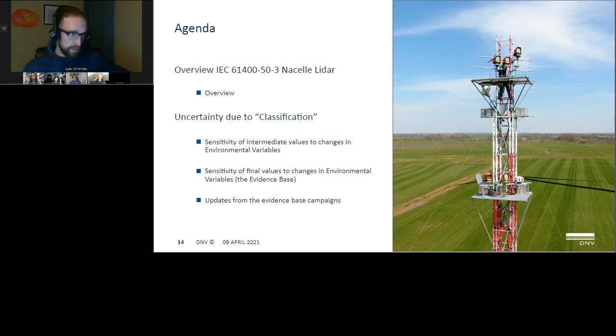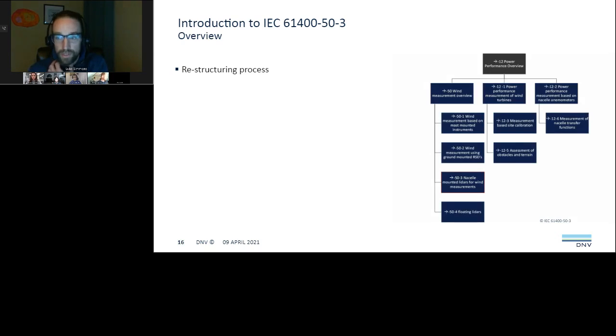If we consider the overview here, currently the IEC 61400-12, the power performance standard, is undergoing a restructuring process. If we look at the new structure, the main thing to be aware of is that the wind measurement methods are being treated separately from the power performance guideline. So there will be one standard for instruments mounted on a mast, one standard for ground lidars, one standard for nacelle lidars where we're focused today, and then another standard here in the bottom left of the framework for the floating lidar measurements.